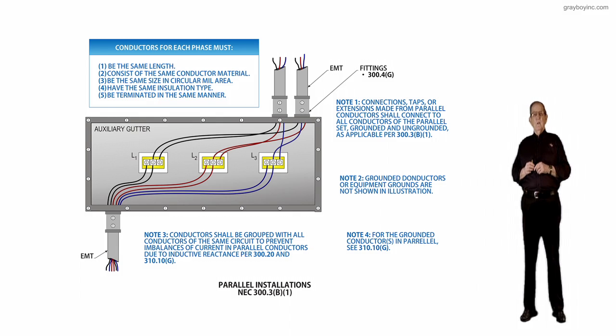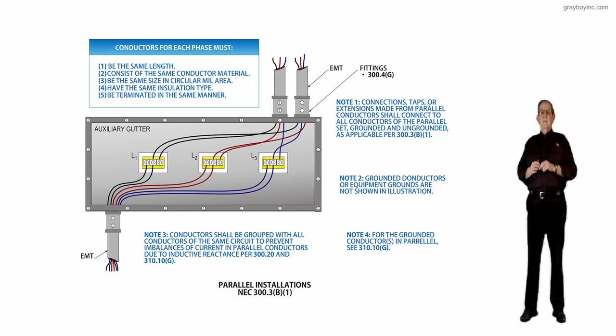Make sure you review the purpose of change very carefully. This new sentence basically requires that the connection for a parallel set of conductors includes all the conductors of the set, not just one of the conductors in parallel as has been done in the past.